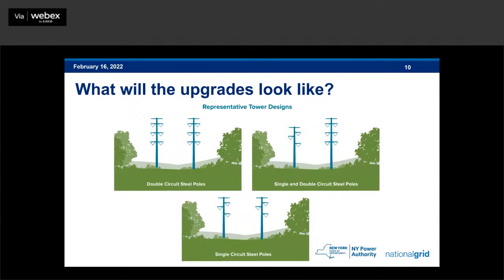The upper left diagram represents a portion of the project from Chateaugay to Clinton, consisting of two double circuit 230 kV lines. The upper right diagram represents the remainder of that same circuit, consisting of a single circuit and double circuit 230 kV lines. But the diagram at the bottom represents the majority of how the rest of the project will look along both the northern and southern segments, with two single circuit structures designed to operate at 345 kV.